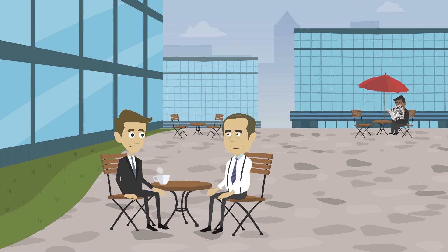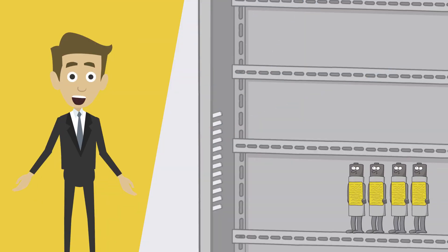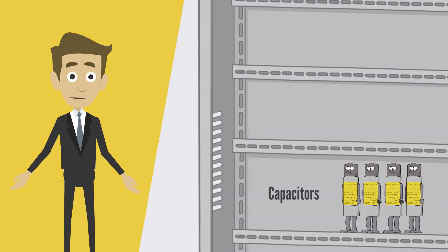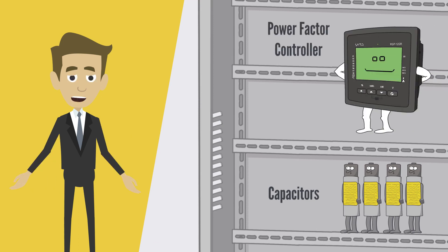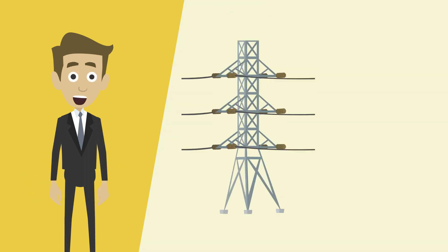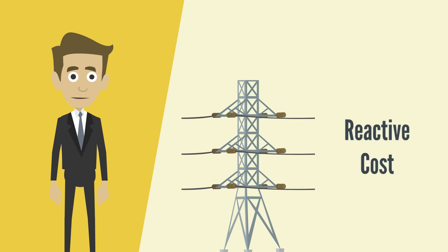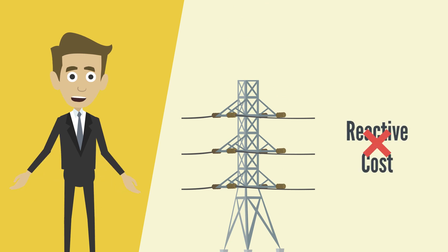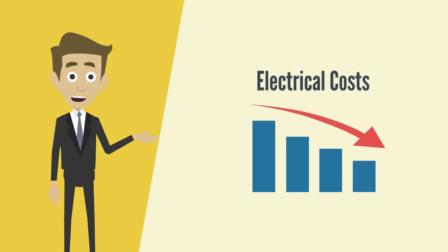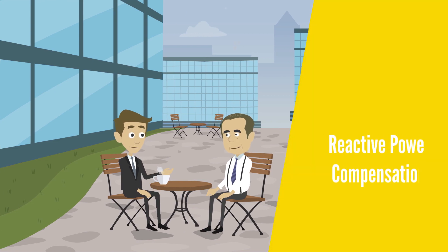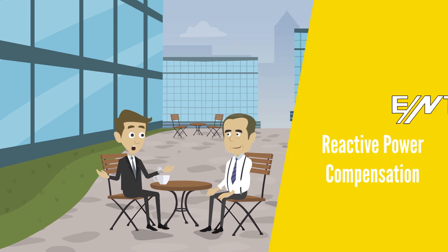Then how can we get the head for the reactive power we need? We do it by installing capacitors on the system and manage these capacitors with reactive power controllers. When we do this, we create no extra load for the main network. Therefore, there are no additional reactive penalties, ensuring that we do not get high bills.